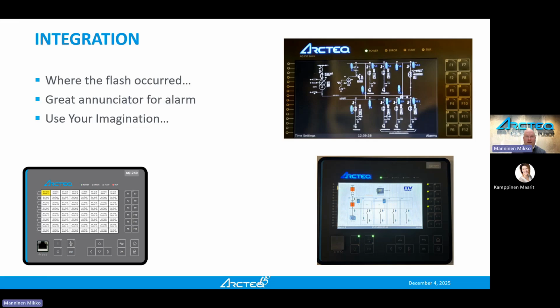So, did you have an ArcFlash in this cable? This sensor is showing it to you, especially when you have an arc quenching device in use. Of course, this arc incident energy is directly related to the time and duration. If the duration is like 4 milliseconds, sometimes it can be difficult to pinpoint where the fault occurred. And if we add 20 times more energy, 20 times that time duration, then you can see other visibility, not on the relay display, but from the door or somewhere else.